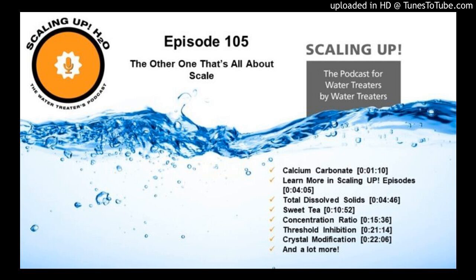And let's say with this product, and it has this threshold inhibition agent in it, we can now extend what the water would naturally hold in solution 10 times out. So maybe we were only able to hold X, now we can hold X times 10. So we are extending the threshold that the water is able to keep in solution because of the threshold inhibitor that we're putting in there.